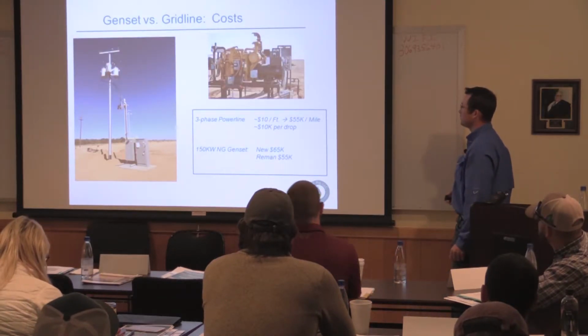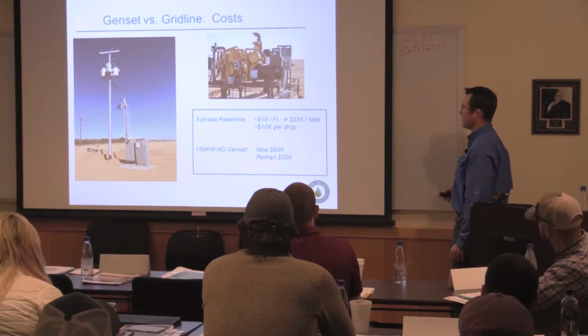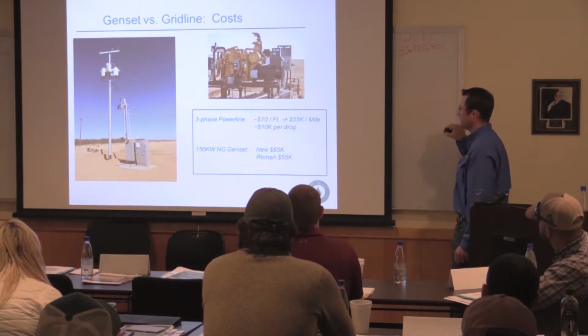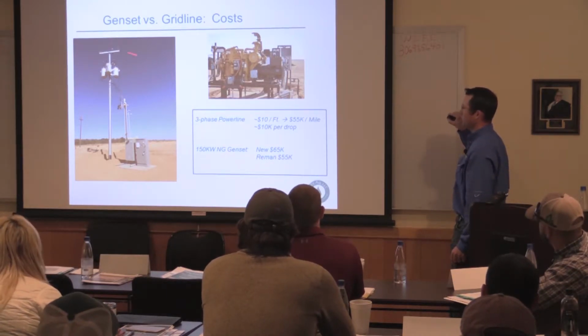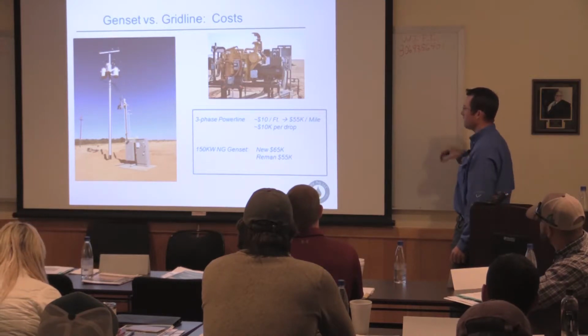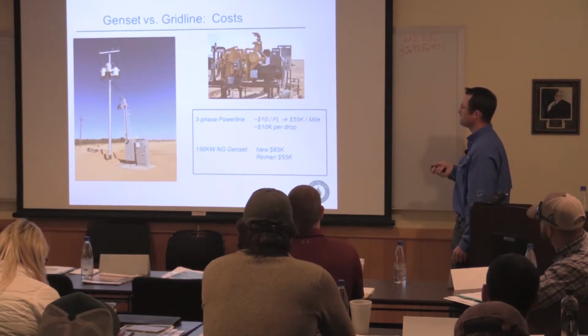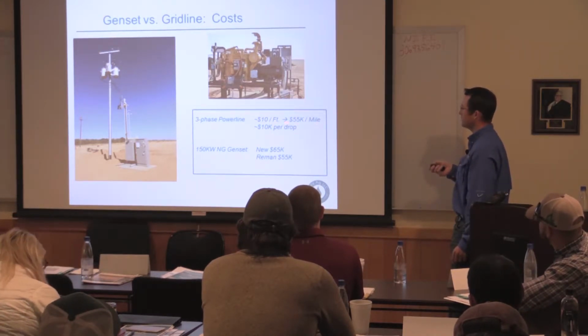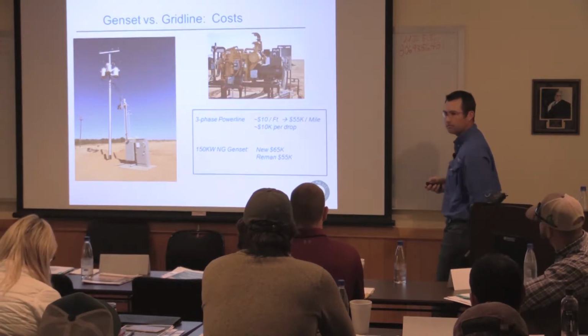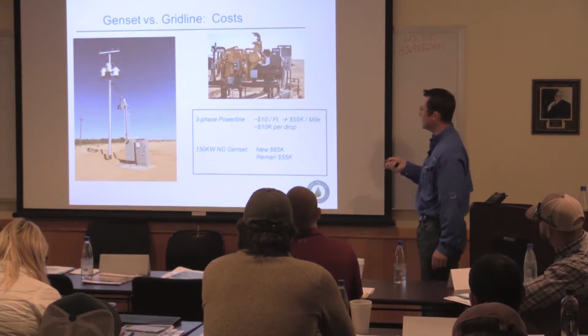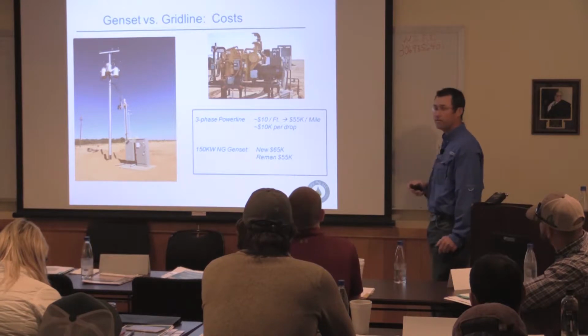Now let's look at some installation costs, the hardware and capital portion. For a 3-phase power line coming in with transformers, run, everything, you're looking at about $10 per foot, give or take, more expensive in some cases, less in others. And you're looking at about $10,000 per 3-phase drop.